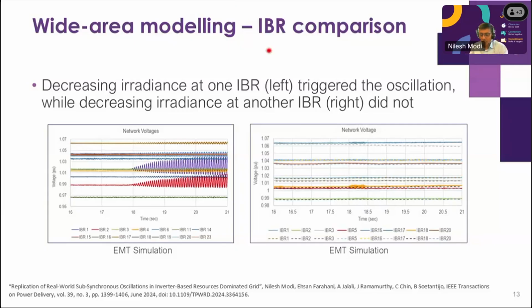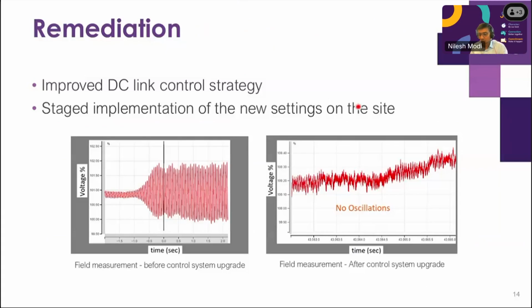Then we started working with various market participants and the OEM. We had a discussion with the OEM and market participants. They looked at their flight recorder data, and they could see there is some kind of thing going on in the DC link control. Working with the OEM, we managed to sort out this oscillation, or at least had a good handle on it. They provided us an improved DC link control strategy, so they improved the control system on the plant. We tested that through the modeling, a similar exercise to what we did in SMIP and the wide area modeling. We repeated that with the new control tuning, and we could see that it is working well as expected.